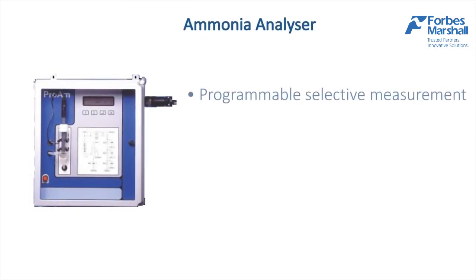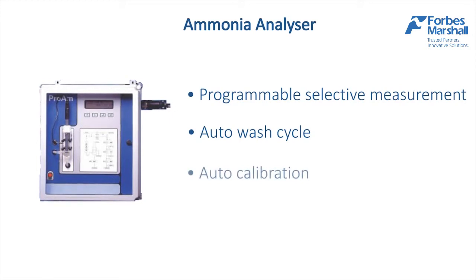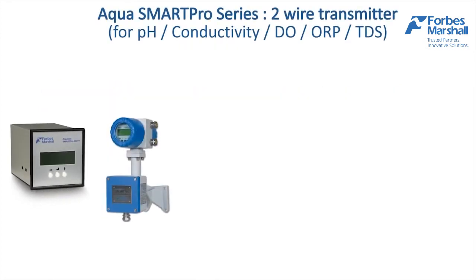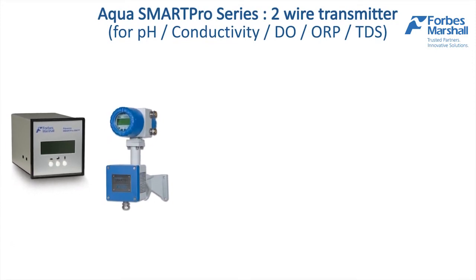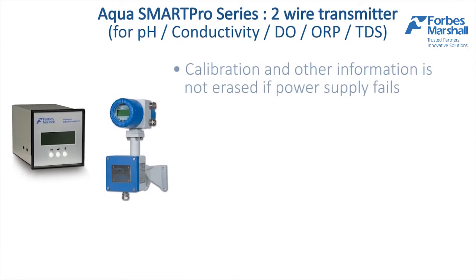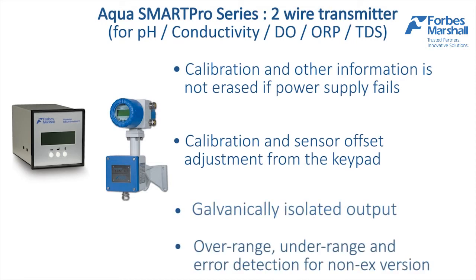The ammonia analyzer provides a specific measurement with an auto wash cycle, auto calibration, and continuous or batch type measurements. The AquaSmart Pro Series two-wire transmitter supports pH, conductivity, dissolved oxygen, ORP, and TDS. Calibration and other information is not erased if the power supply fails, and sensor offset adjustment can be done from the keypad. The output is galvanically isolated with over-range, under-range and error detection.